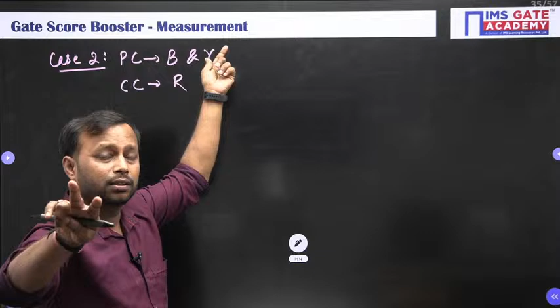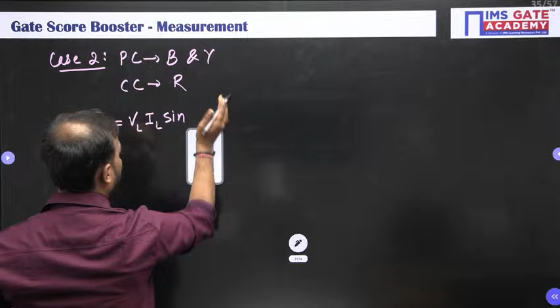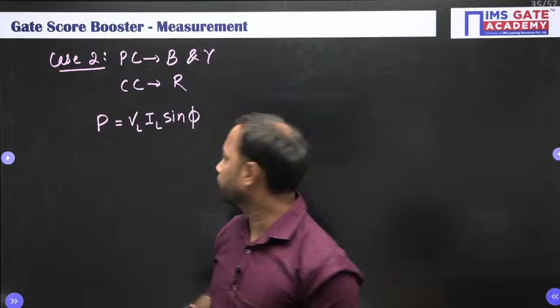Now, please listen to me very carefully. When the pressure coil is connected between two lines, whereas the current coil is connected in only one line, which is the remaining line, see R Y B. You took B and Y in the pressure coil, so what is left? R phase. So in such cases, your wattmeter will read VL IL sin phi. Please do not get confused with P. It is just a notation. I can use my name, Nikhil, here. It is just a notation. Now, VL is the line voltage, IL is the line current, and sin phi.